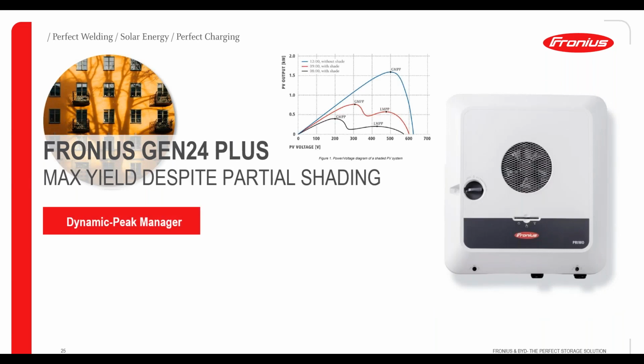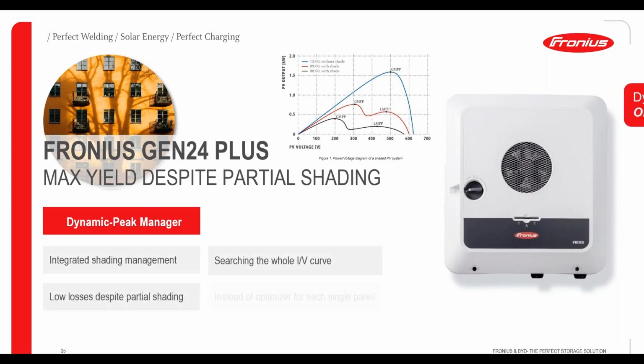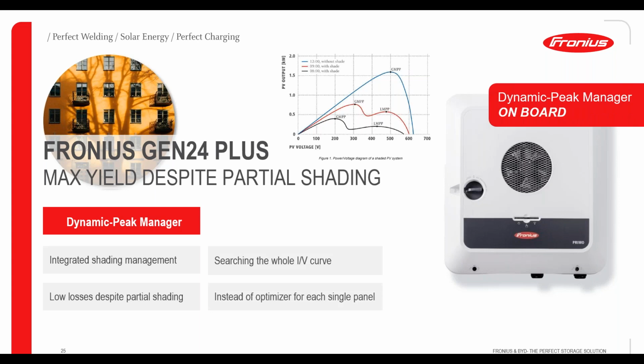All of our inverters are delivered with something that we call Dynamic Peak Manager. In short, that is an answer to the optimizers that you can put at the panels. So instead of having the optimization at the panels, we actually put it in the inverter. Basically, the inverter is searching the whole IV curve to see if we can boost this string up a little bit, maybe gaining more solar production. And this is done all the time through the day.